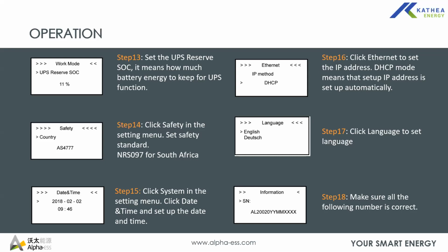And from that work mode, you can actually select your UPS reserve SOC. This is the battery SOC that you would like to use only when you have load shedding. So this value depends on which area you are in and how erratic your load shedding program is. If you experience a lot of load shedding, definitely you need your battery to always have a high SOC to back you up when you're on load shedding. But if you're in areas where there is less load shedding, then you can set the reserve SOC a bit lower so that you can fully utilize your PV system.